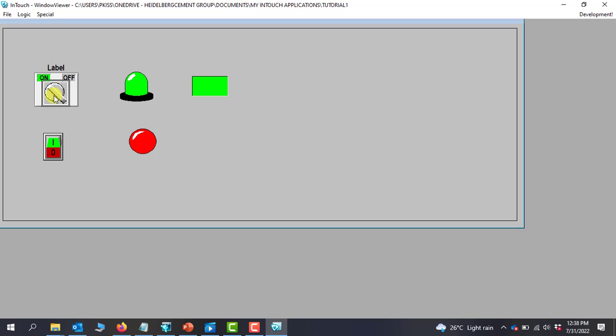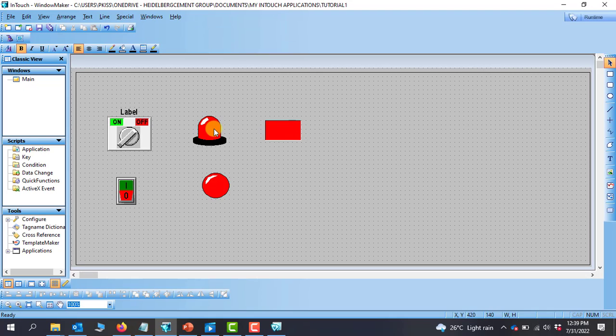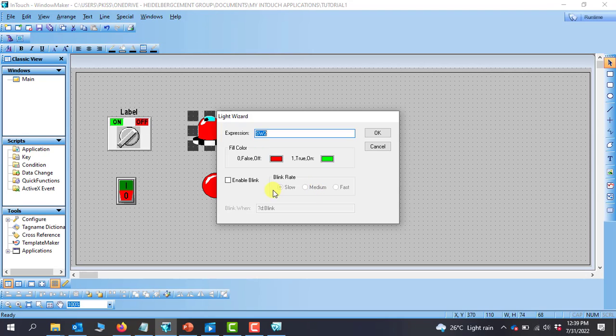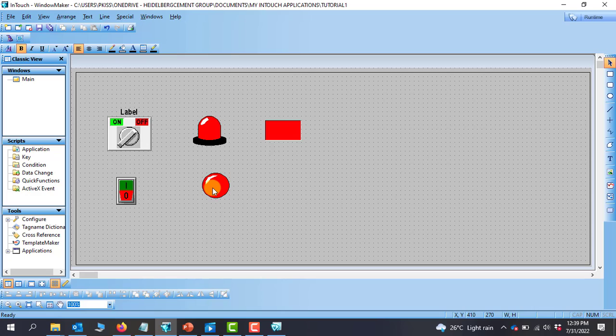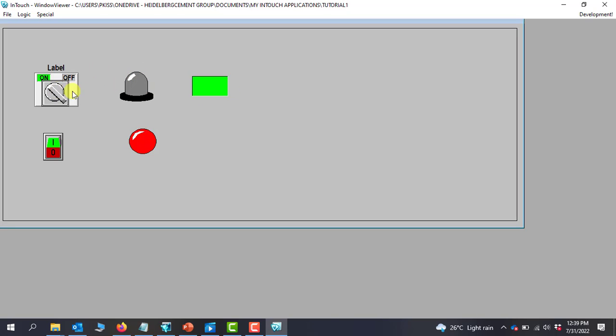Now sometimes you want to add a bit of animation. Instead of the lamp being green constantly on, you would like it to blink, indicating other states. So let's try that. I'll go back and when I click on this lamp we can see that we have enable blink. So I have to click on it and then specify which condition will cause this lamp to blink. It's basically when the switch is turned on, so I can then specify switch two here. Let's go on the runtime and see. So we can see that the lamp is on and then it's flashing. When I go off, this remains off. And when I come on, we can see it flashing. So we can see how easy it is to cause the devices to flash using this approach.